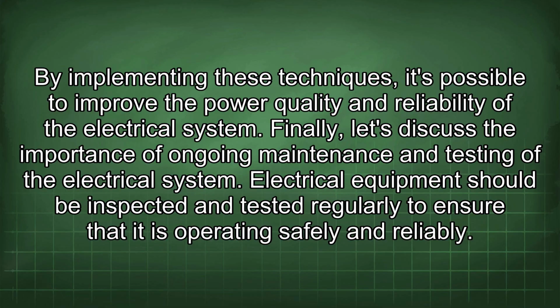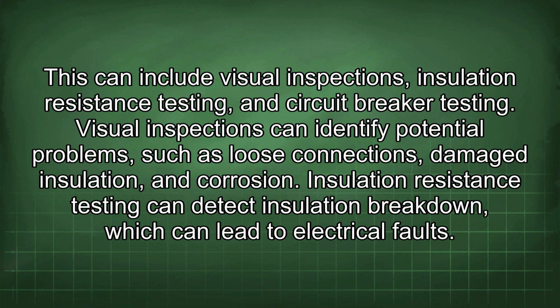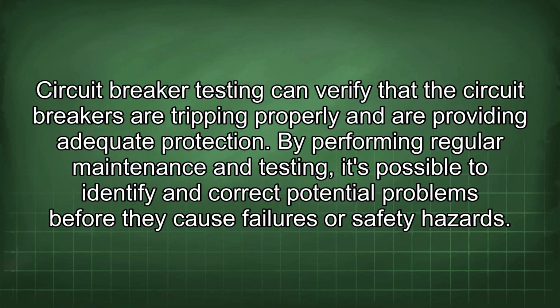Finally, let's discuss the importance of ongoing maintenance and testing of the electrical system. Electrical equipment should be inspected and tested regularly to ensure that it is operating safely and reliably. This can include visual inspections, insulation resistance testing, and circuit breaker testing. Visual inspections can identify potential problems such as loose connections, damaged insulation, and corrosion. Insulation resistance testing can detect insulation breakdown, which can lead to electrical faults. Circuit breaker testing can verify that the circuit breakers are tripping properly and are providing adequate protection.